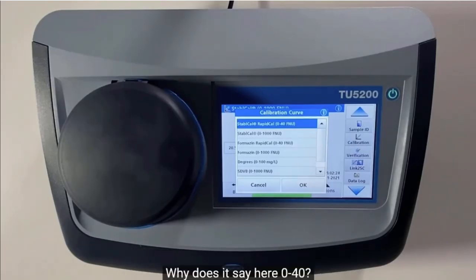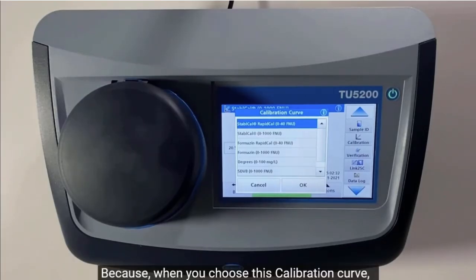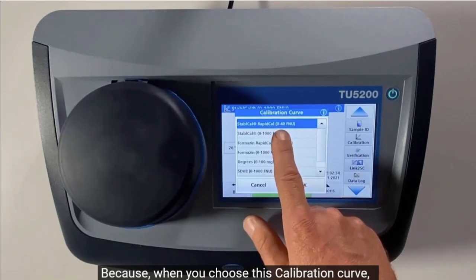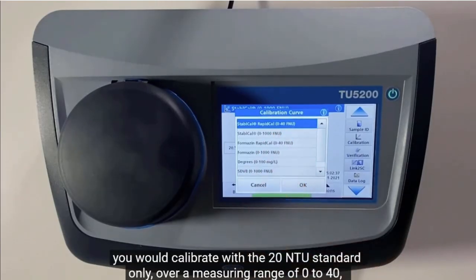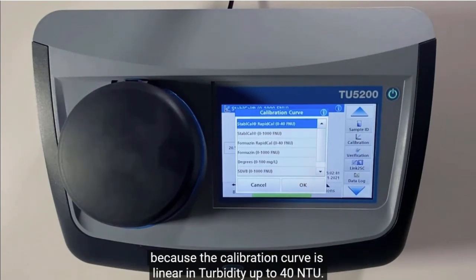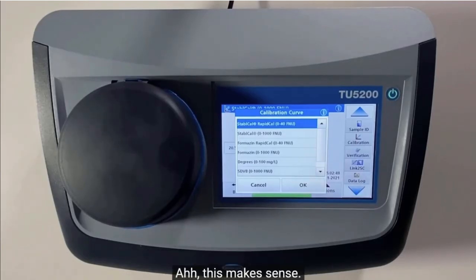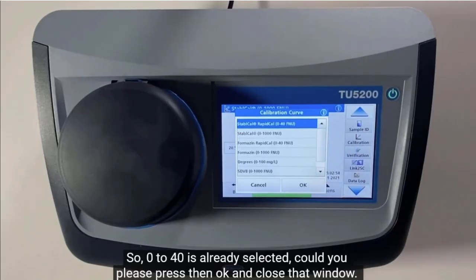But why does it say 0 to 40 here? Oh, yeah, that's a good question. You mean this 0 to 40 here? Yes. Because when you choose this calibration curve, you would calibrate with the 20 NTU standard only over a measuring range of 0 to 40, because the calibration curve is linear in turbidity up to 40 NTU. Ah, this makes sense. Should we do this calibration? Yes, please. Okay. So 0 to 40 is already selected. Could you please press OK and close that window?